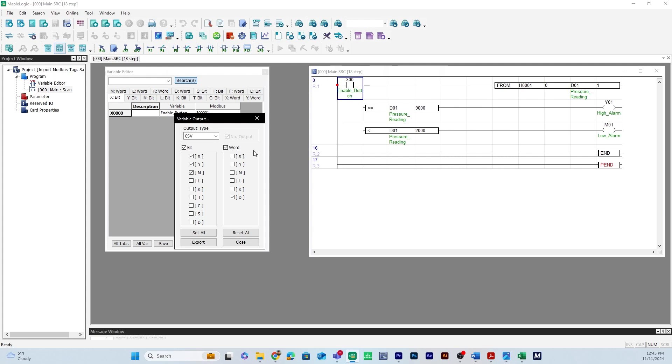An important thing to know is that Easy Builder Pro will only recognize Modbus addresses like 0x, 1x, 3x, or 4x. A really great thing to know is that Maple Logic automatically maps X and Y to 0x and 1x Modbus addresses and M and D to 3x and 4x registers.